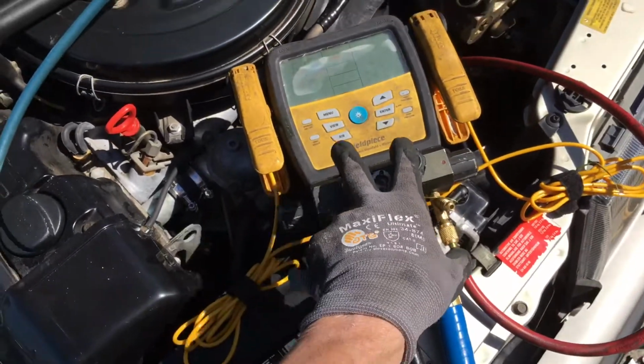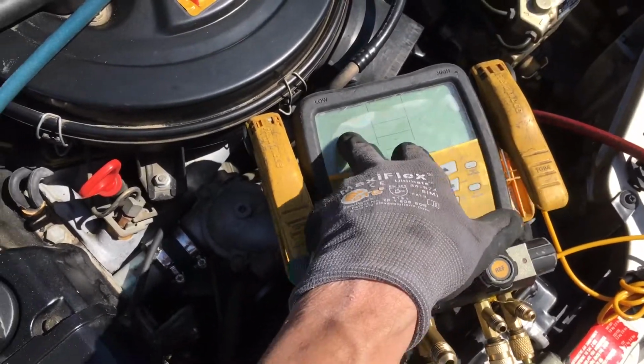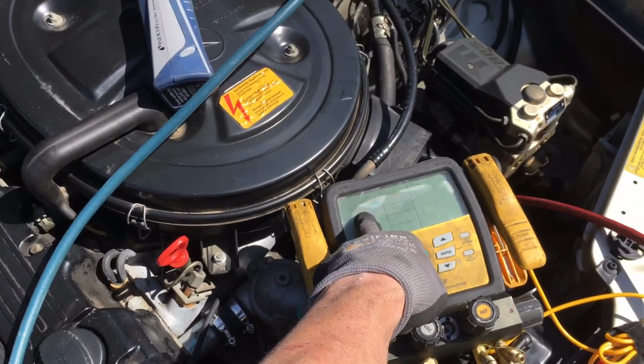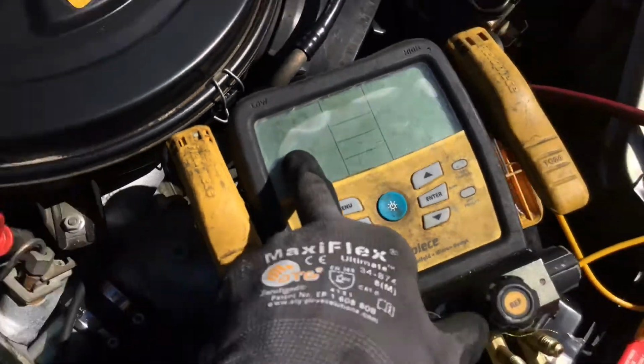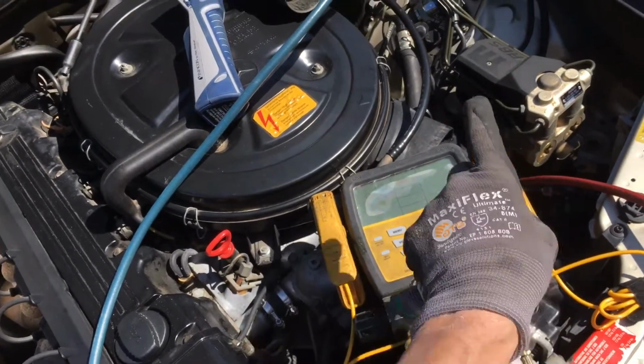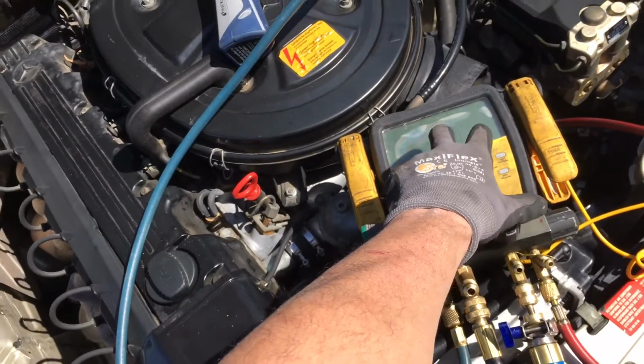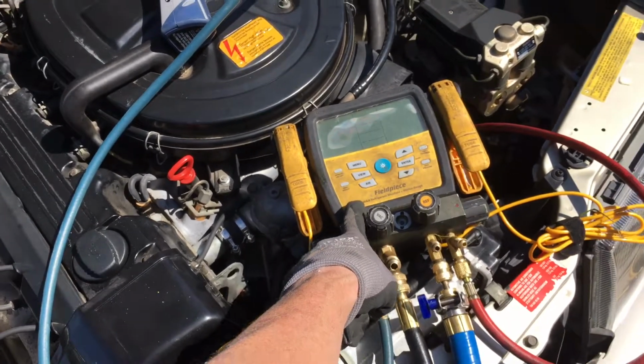You can't see because my Fieldpiece gauge recently suffered an injury of moisture, as you can see from the little bit of residue of condensation on the inside of the glass. I can barely make out the numbers, 630 or 627, 624, 25, 23. It's going down. That's the micron level right here that you can barely see. I don't know if the camera can see it, but my eyes can see it there. Yeah, I'm going to take one of these apart, and I'm going to get some circuit board sealer for marine application. I'm going to see if I could spray everything under here and protect it from moisture. They really got to work on an IP68 or whatever it's called, moisture resistance of these Fieldpiece gauges. That's the next step they have to go to, something that's a little bit more robust.